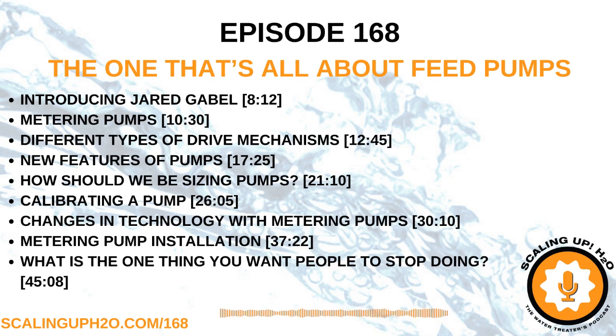And one of the cool things is when you actually tell the pump to speed up or slow down, we can do that on the different suction and discharge phases because of the stepper motor. So we can say, all right, when you go through a suction phase, let's bring it back quickly because we want to get back to putting chemical in the process. And then when you take advantage of the turndown ratio, we can start putting that in very slowly, which actually reduces the need to install things like variable speed drives or static inline mixers or pulsation dampeners, because we're now reducing all the needs for those things that we would normally have to install.